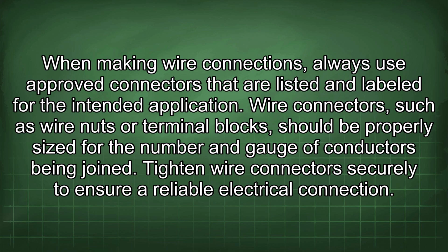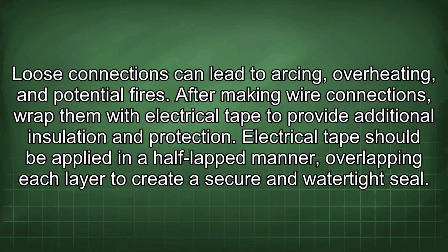When making wire connections, always use approved connectors that are listed and labeled for the intended application. Wire connectors, such as wire nuts or terminal blocks, should be properly sized for the number and gauge of conductors being joined. Tighten wire connectors securely to ensure a reliable electrical connection. Loose connections can lead to arcing, overheating, and potential fires.